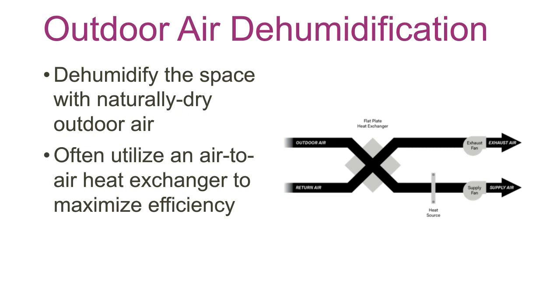So in the version of outside air for dehumidification, you're going to bring the outside air and dehumidify it with the naturally dry outdoor air rather than use compressors. Very often you're going to have an air-to-air heat exchanger in there for energy efficiency because you're using a fair amount of ventilation air. So the little schematic here is actually the 100% outside air version.